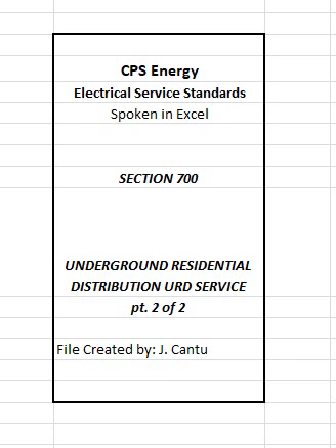Where the proposed service lateral is greater than 250 feet, and the transformer or secondary enclosure is located on an adjacent property, an additional transformer or secondary enclosure may be installed on the customer's property, at customer's expense, to minimize the service lateral length. This additional transformer or secondary enclosure shall be installed at the closest property corner to the existing transformer or secondary enclosure. Only one secondary enclosure will be permitted on a property.